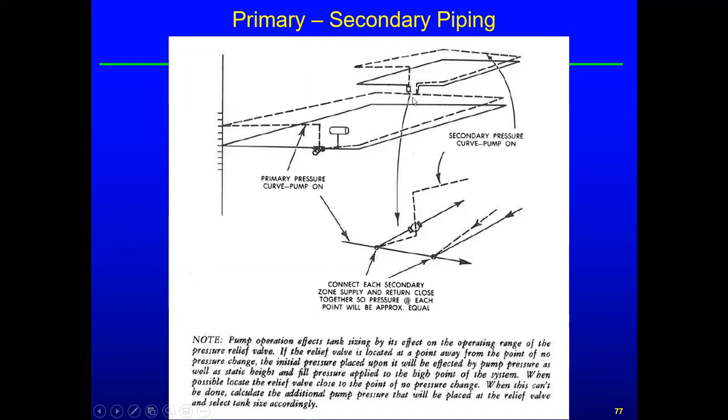And so when you connect this secondary, you want these connections to be as short as possible, okay? Because you don't want any pressure drop between your secondary supply line coming off and your secondary return coming back in. Because if I don't want any heat in this circuit, I just turn this pump off. Well, the only thing that would cause flow by this from the primary would be a pressure drop. If I make this a 10-foot section of pipe from here to here, there's going to be pressure drop, right? Because I got frictional drop in my primary. Well, if I have a pressure difference from there to there, then that pressure difference will force a small amount of flow back up here, and I'll flow my secondary when I don't want to. And so if the pump's off, it's because my secondary doesn't need any heat. I turn the pump off, but I got a pressure drop, so I get heat anyway. So I don't have good control on the secondary if I do that. So that's why we want these points of connection to be very, very close together.